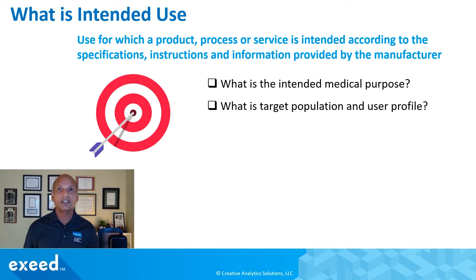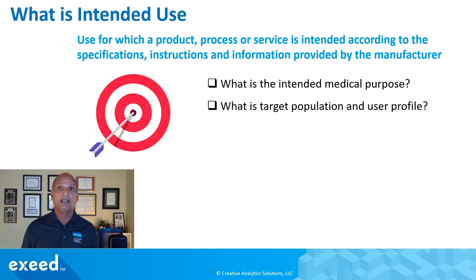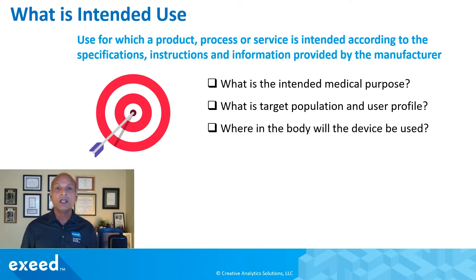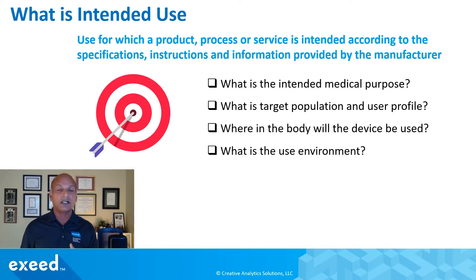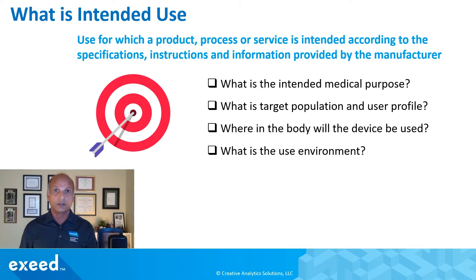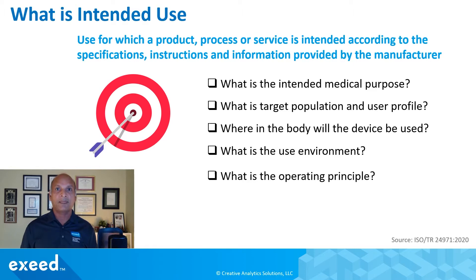What is the target population and user profile? Maybe there's a certain demographic or age range — if it's meant for a pediatric population, it needs to specify that. Are users experts or common consumers? Where in the body will the device be used — is it an implant or a disposable single-use device? What is the use environment: at home, in a hospital, in an intensive care unit, or used by first responders in the field? And what is the operating principle — how does it work at a higher level?